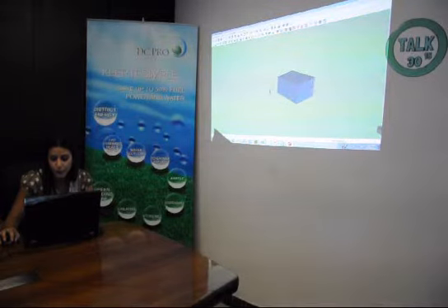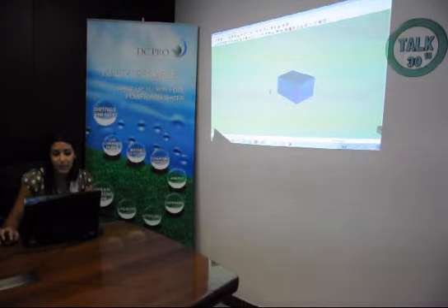And now what you can do is that if you want a space type that is not in our template, I can go to Plugins, OpenStudio User Script, you have to create an account to use these user scripts. Go to building components library and get a space type. Here, you can create your own space. I'm going to use ASHRAE 90.1, this climate zone, and let's see if we make the space a supermarket. Now it's going to download all of the schedules, the constructions, the loads that are associated with that space type.